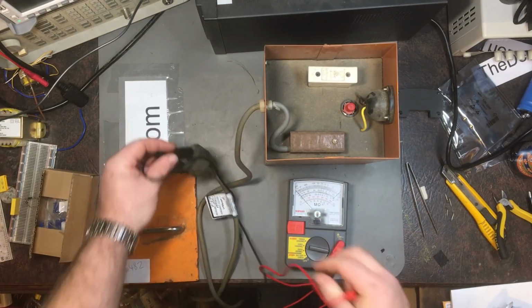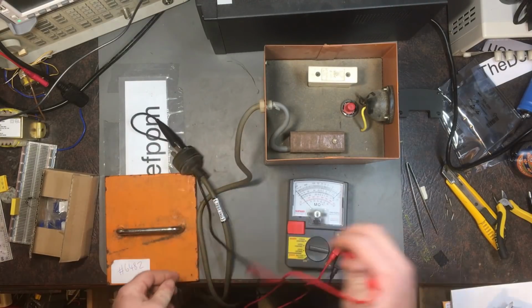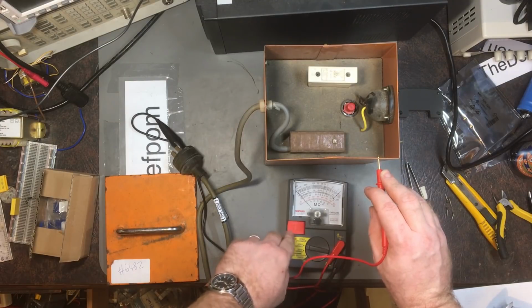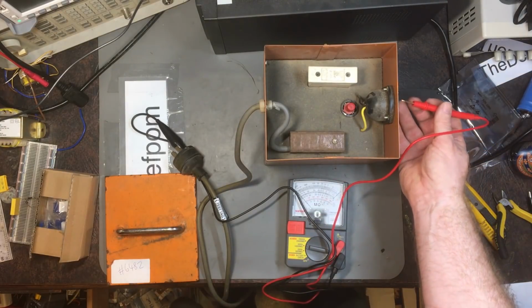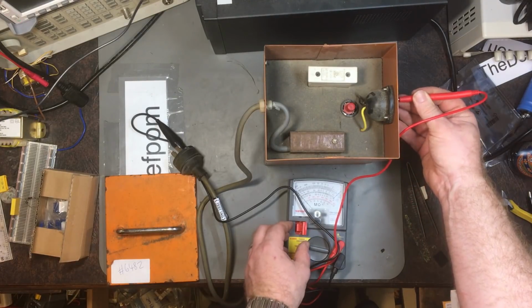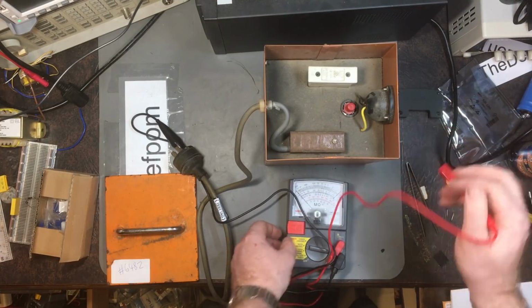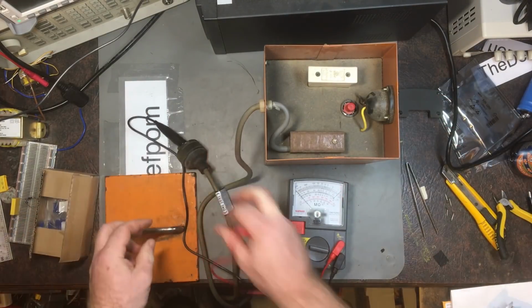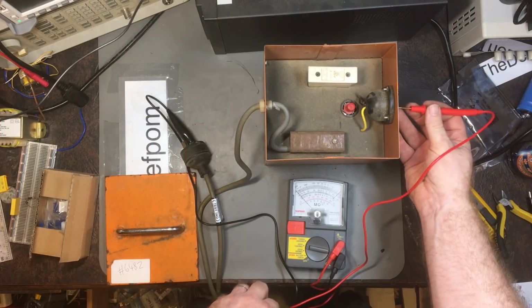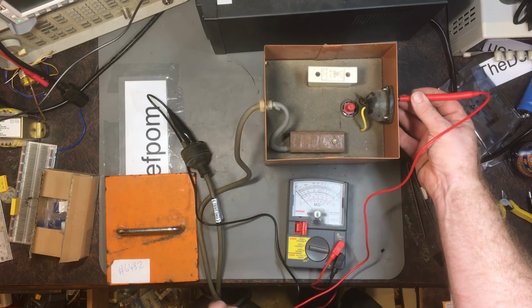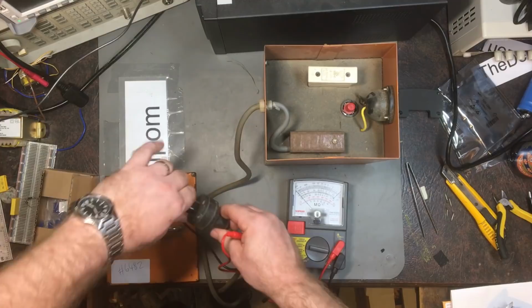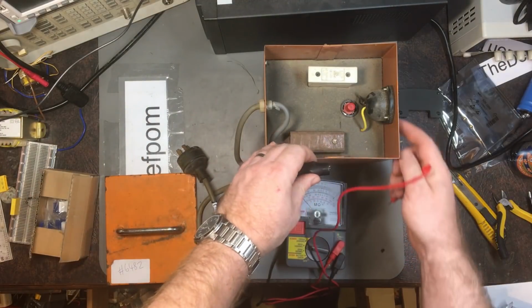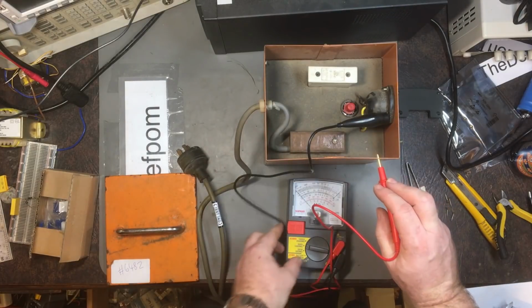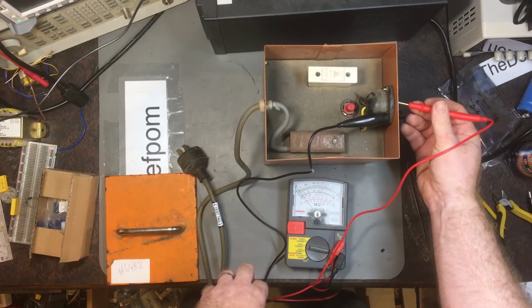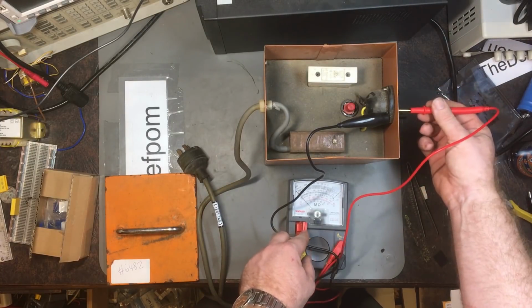Yep, that's fine. The other side, casing - yep, that's fine. So we'll check the output connections. Nothing there, nothing there. Check the other side as well - nothing there, nothing there. Also I want to check from the casing to the other side, so I need an earth point, which that probably is - I'll find out. Yep, so check there as well - nothing, and nothing. Okay, insulation resistance looks fine.